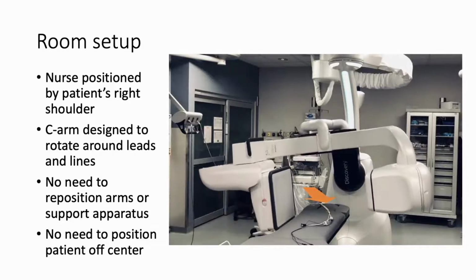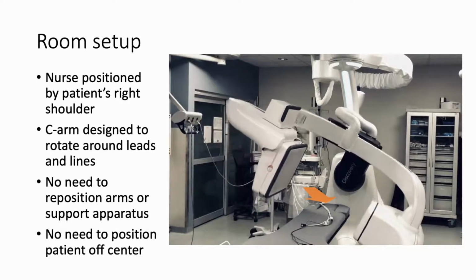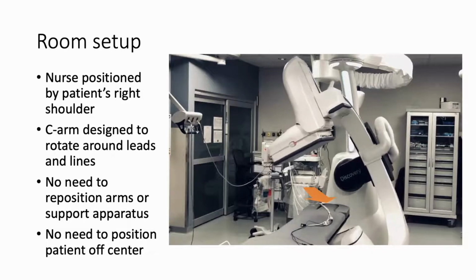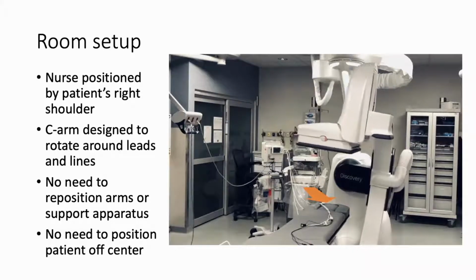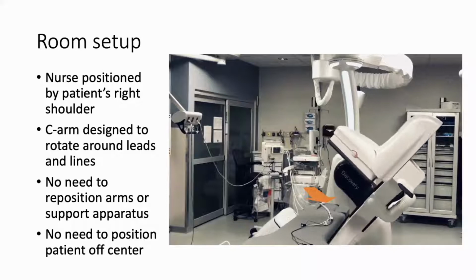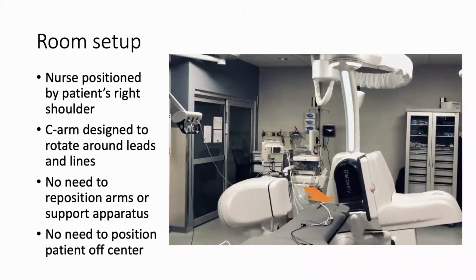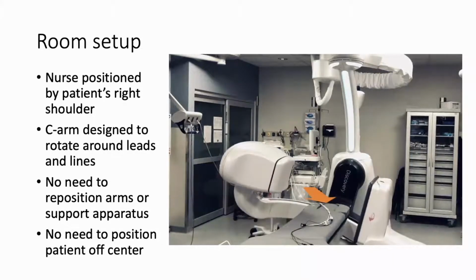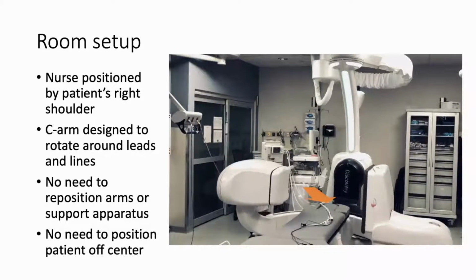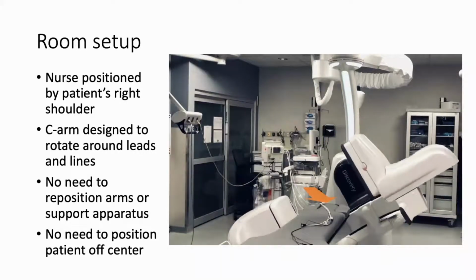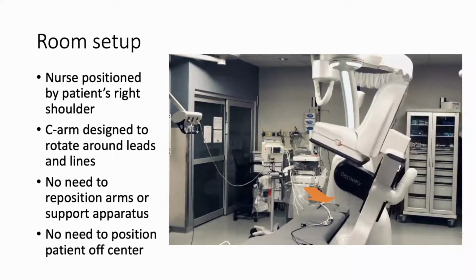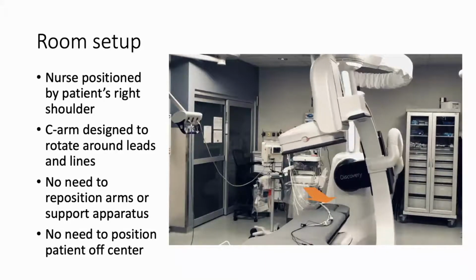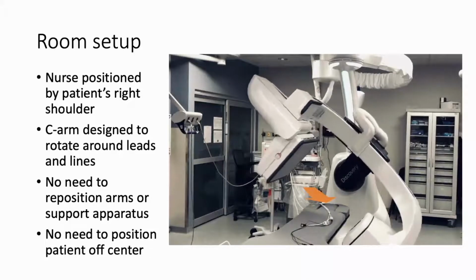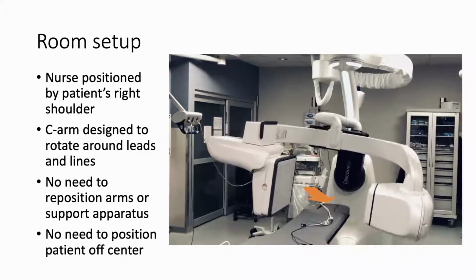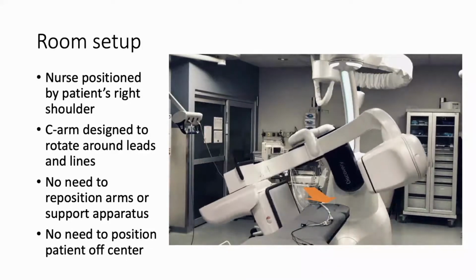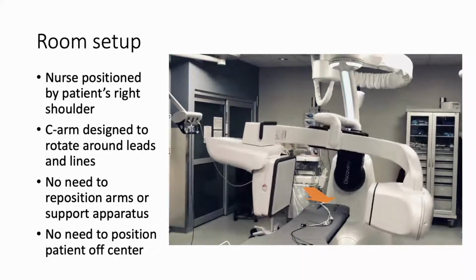So what I want to illustrate here is where this case efficiency comes from. So our room setup is shown here. The nurse is positioned by the patient's right shoulder, and note the geometry of the C-arm. The C is offset to the left side of the source and detector. And this is really clever because it means that the sweep rotates around the leads and lines, which are running along this orange arrow towards the nurse's station. So therefore, there's no need to reposition the arms or to reposition support apparatus because the C-arm will rotate around them.